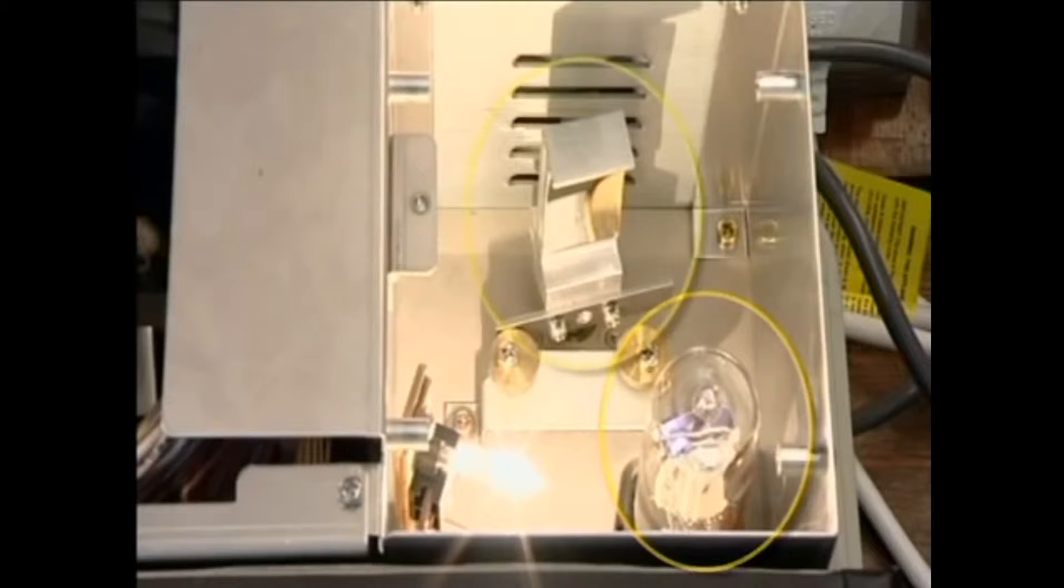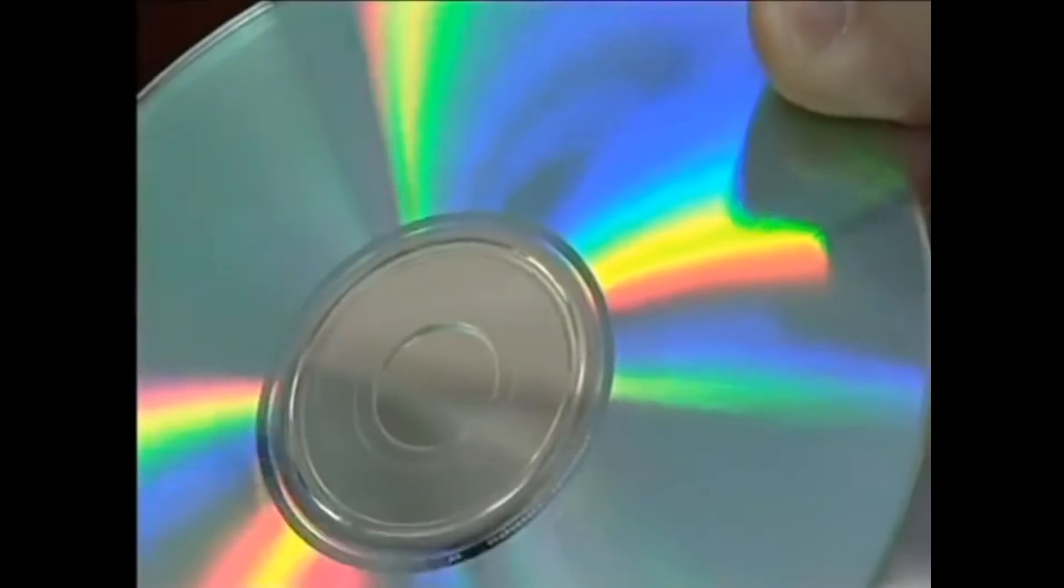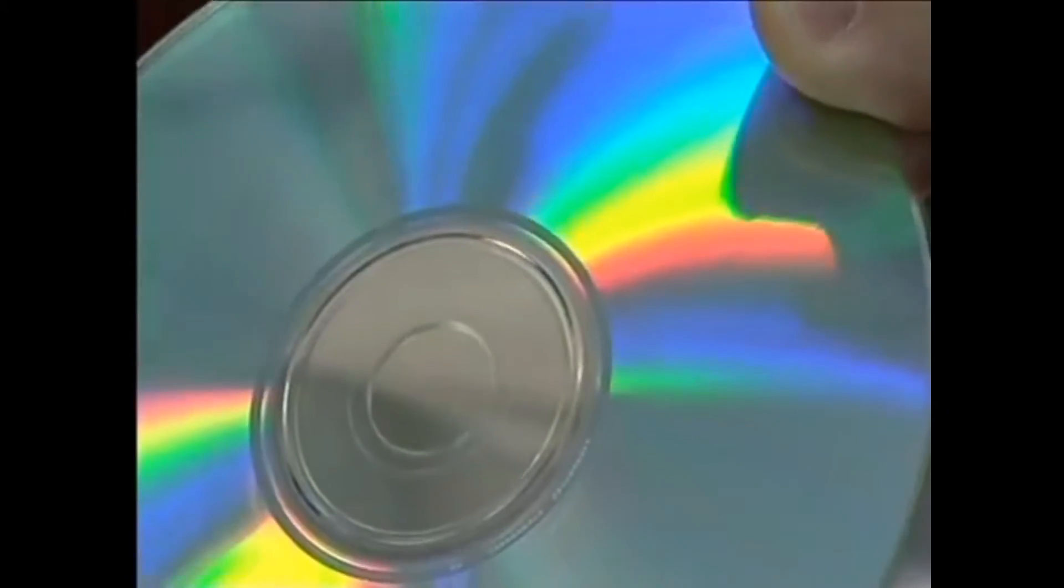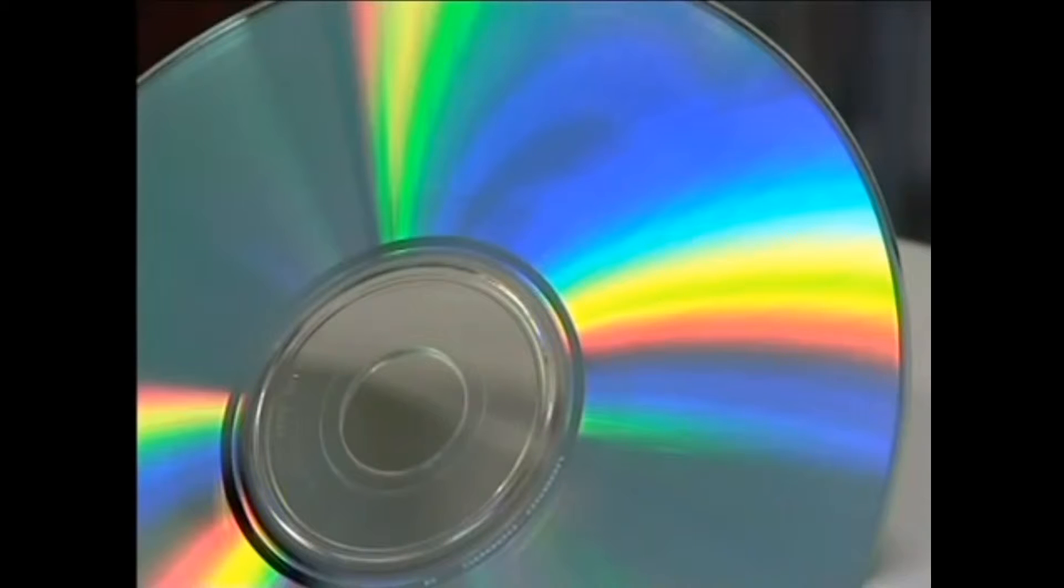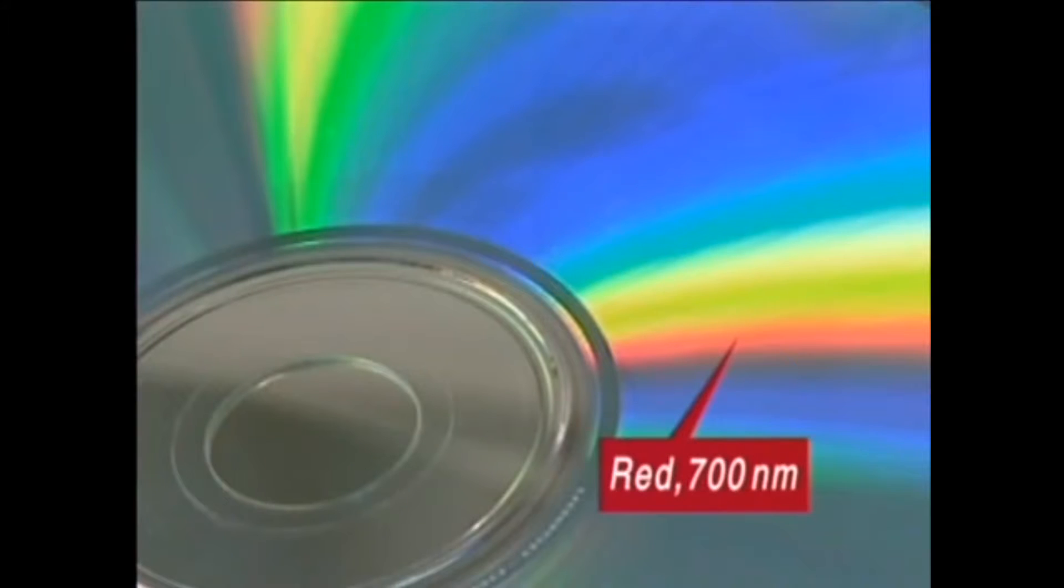This mirror directs light from the appropriate source into the monochromator, which contains a diffraction grating that acts like the playing surface of a CD to split the light into its constituent wavelengths. Different wavelengths correspond to different colours - red is about 700 nanometres and blue around 400 nanometres. Wavelengths shorter than about 350 nanometres are called ultraviolet. Shorter wavelength light has higher energy.